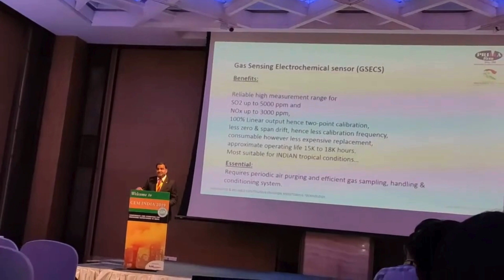And I'll show you the statistics of what we have done in our laboratory using this. The most concern is about the replacement of some components of the sensor or analyzer because they have a shelf life. So here we have considered the replacement of the sensor consumable at 15,000 to 18,000 hours. And this is practically being monitored. It is better, it's more than that. In some cases, where you have a very clean application, it can go up to 20,000 also. I'm taking this figure as the worst application.